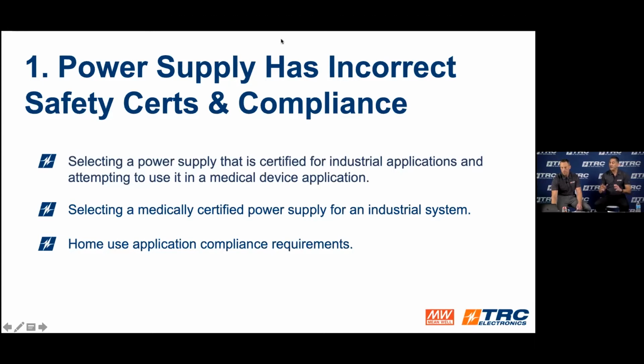So you see here, Steve, what typically happens is those two agency certifications, UL 62368-1 and 60601-1, are very similar, but there are actually two differentiators that medical power supplies need to have inside the power supply.